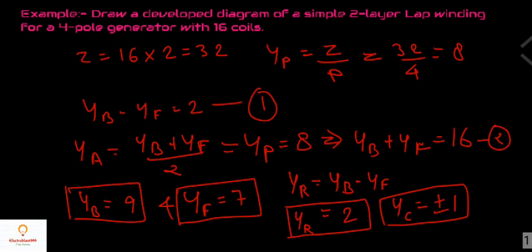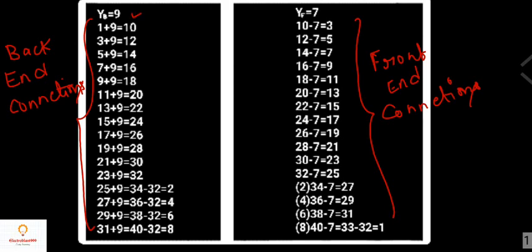Now let us draw a simple winding table for this question. We have back pitch equals 9 and front pitch equals 7. These are our back-end connections and these are our front-end connections. At the back end, back pitch is 9, so starting from conductor 1: 1 plus 9 equals 10 at the back end. Front pitch is 7, so 10 minus 7 equals 3. Again at the back end: 3 plus 9 equals 12, and at the front end: 12 minus 7 equals 5.